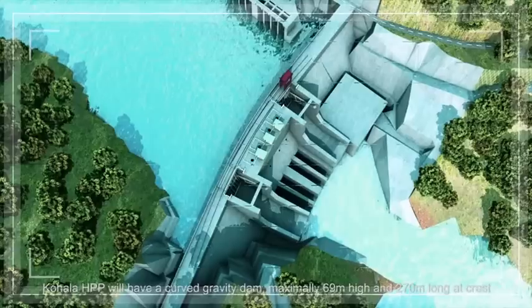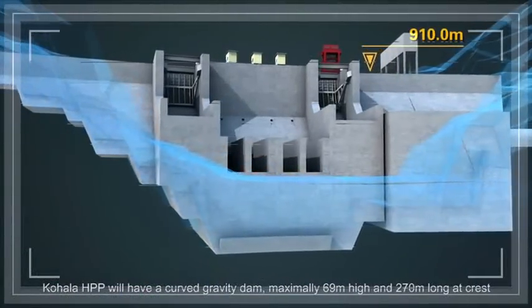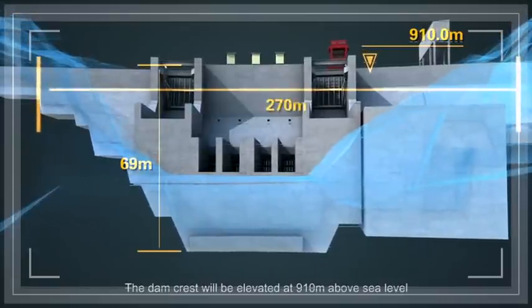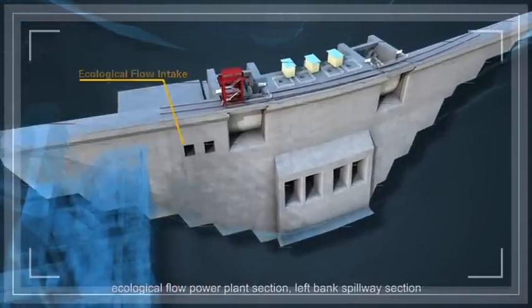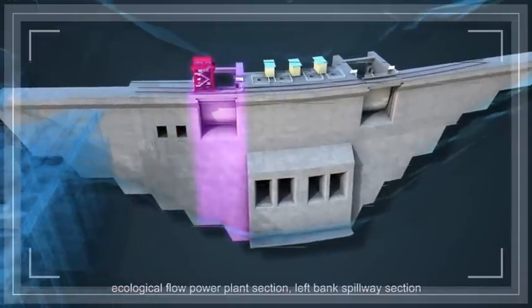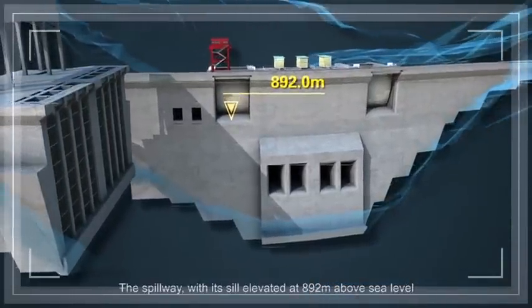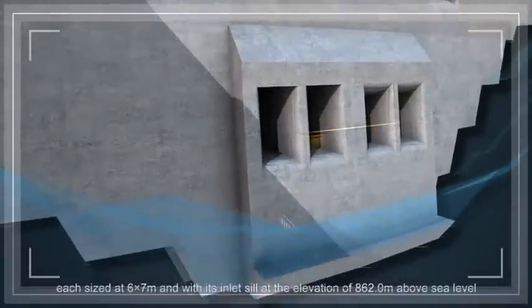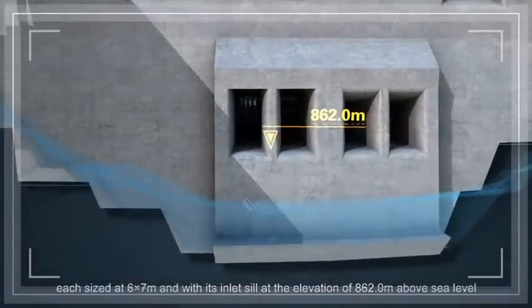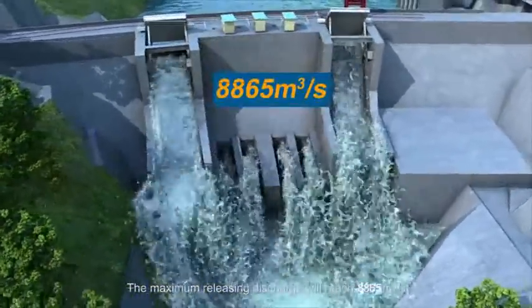Kohala HPP will have a curved gravity dam, maximally 69 m high and 270 m long at crest. The dam crest will be elevated at 910 m above sea level. From left to right, the dam will be composed of left bank non-overflow section, ecological flow power plant section, left bank spillway section, low-level outlet section, right bank spillway section, and right bank non-overflow section. The spillway, with its sill elevated at 892 m above sea level, will have four bays, each sized at 15 x 15 m. There will be four low-level outlets, each sized at 6 x 7 m, with its inlet sill at the elevation of 862.0 m above sea level. The maximum releasing discharge will reach 8,865 m³ per second.